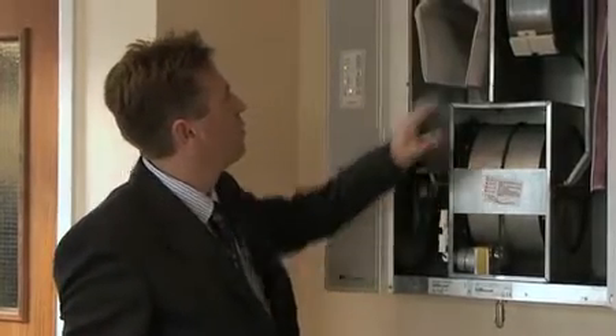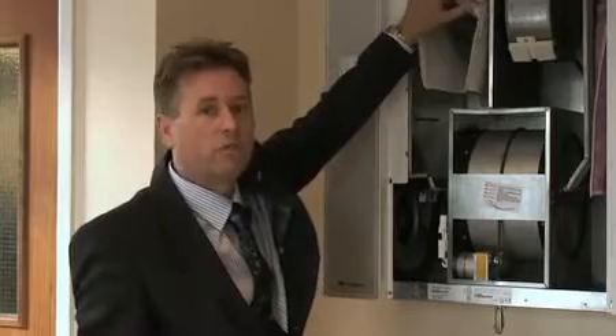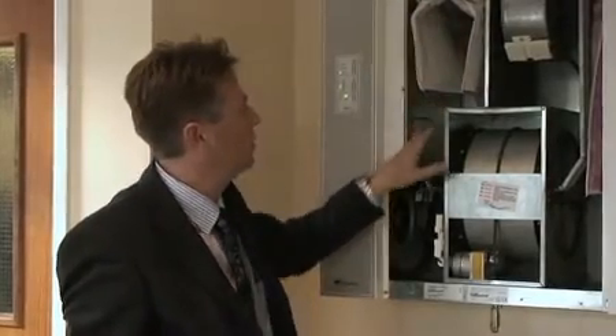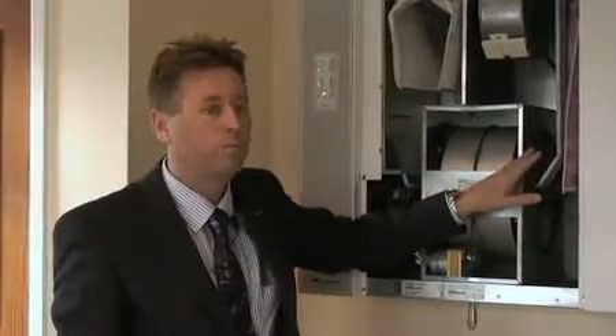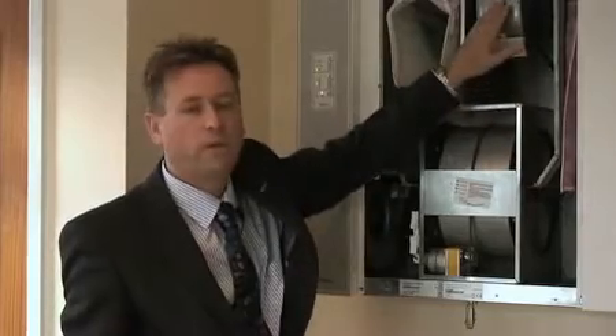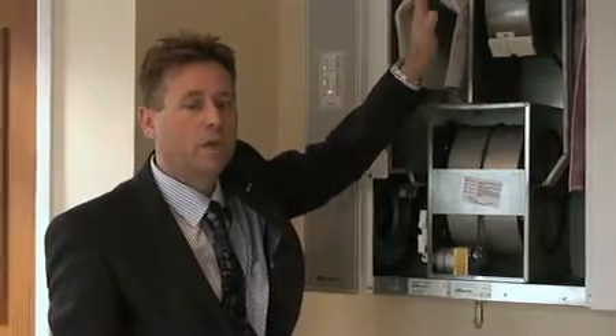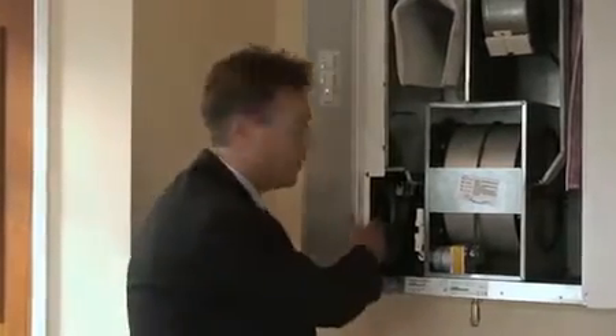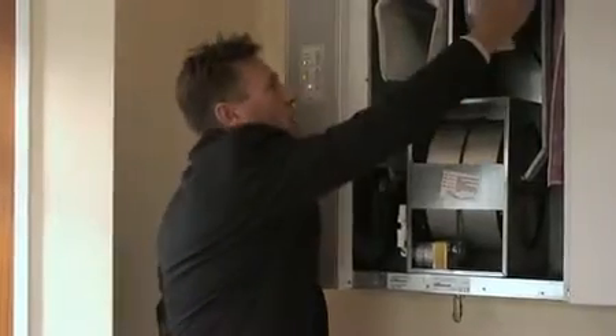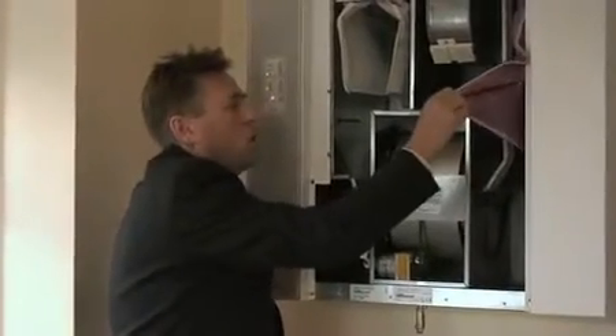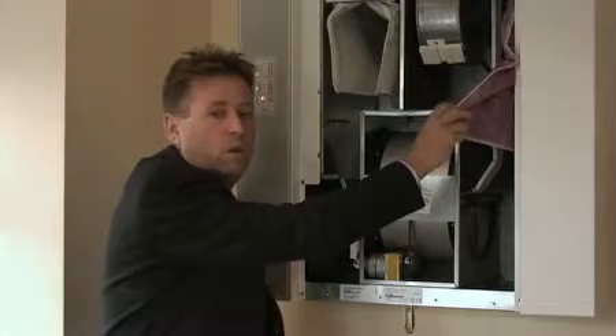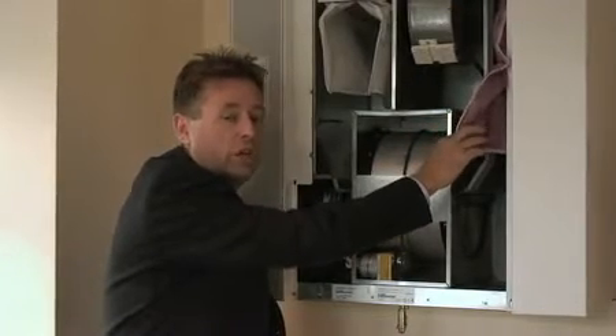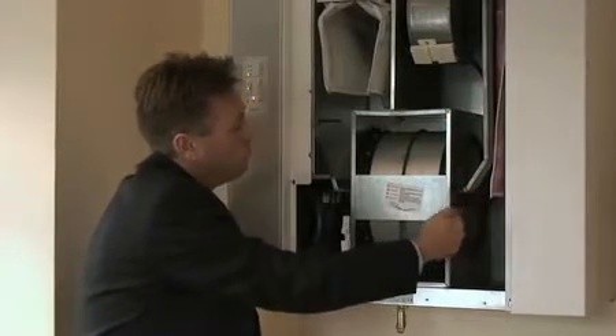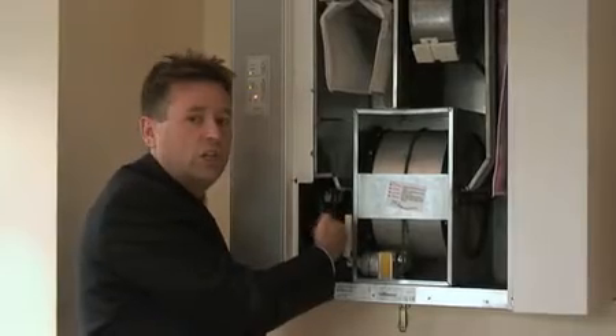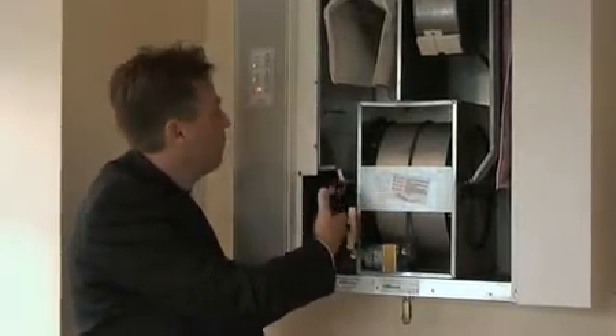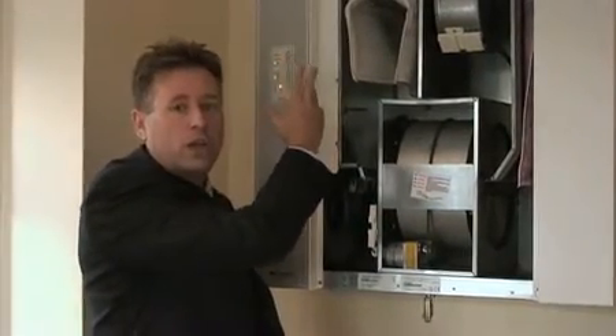In principle, we're extracting the wet air from the bathrooms and shower rooms through the filter, through the rotary wheel, where all of that air is sucked in by the fan and blown out to outside. At the same time, this fan unit here is sucking fresh air from outside across a very good filter, which is approved by the British Allergy Foundation, drawing the fresh air across the heat exchanger, collecting the heat before blowing the warmed, filtered fresh air back around the house.